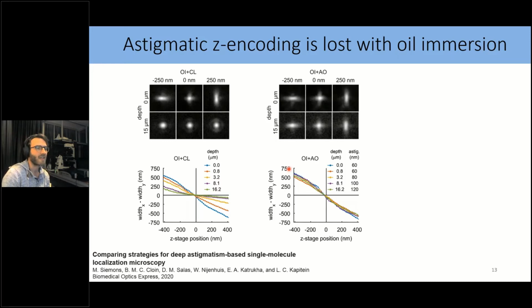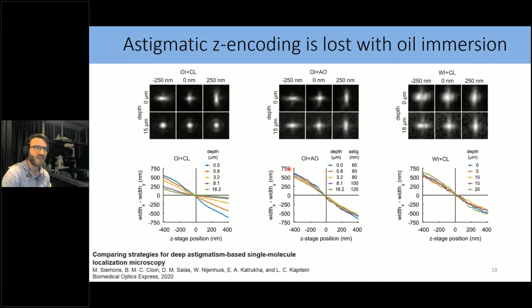Interestingly, if you use a water objective and a cylindrical lens, you also maintain the same calibration curve. So this already indicates that the spherical aberration introduced by the mismatch of the refractive index of your immersion medium as well as your sample is the main root cause for this loss of ellipticity.